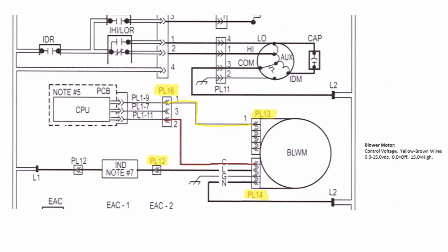This is a wiring schematic from one of the major manufacturers of a single communication line to the ECM motor. Most manufacturers will have troubleshooting guides that will give the voltage value that you should see on these wires. In this case, between the yellow and brown wire in the off cycle, you will see 0 voltage DC, and when the motor is commanded to run at high speed, you will see 15 volts DC.